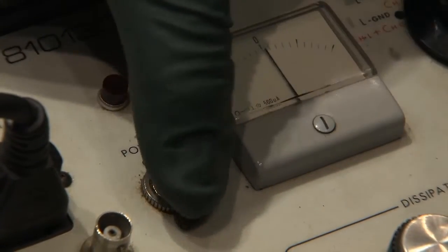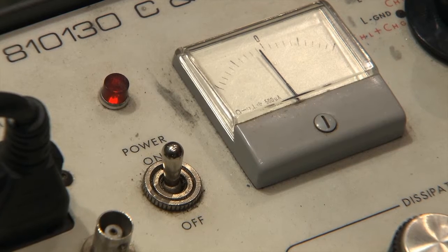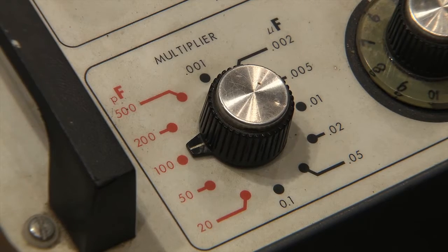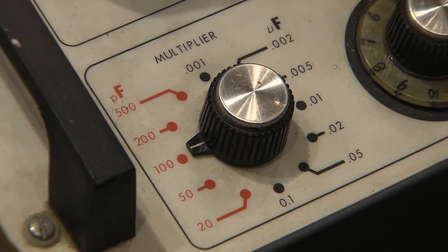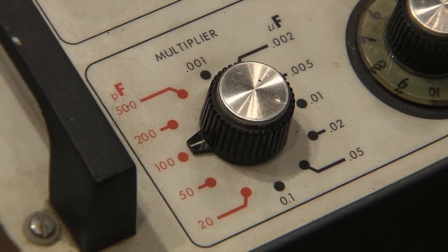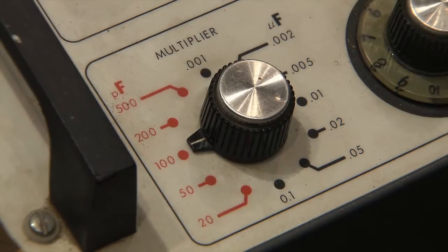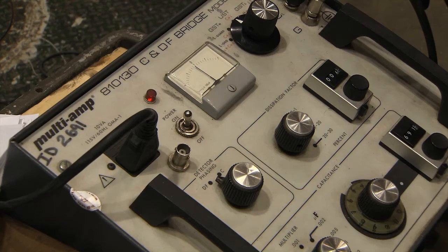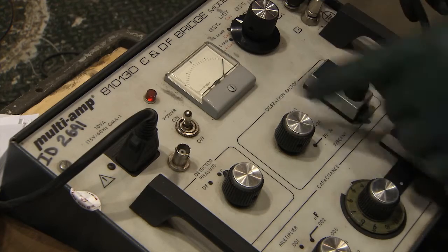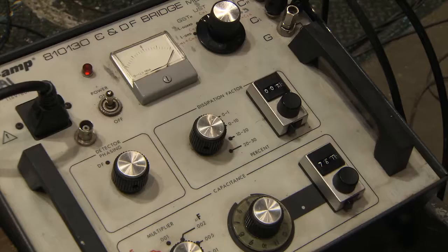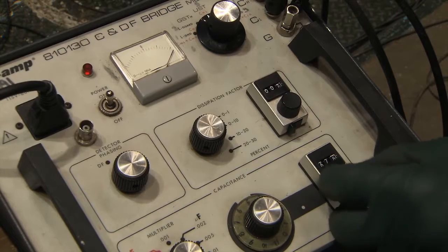Begin by turning the power switch to on. Okay, it's on capacitance right now. Dial the multiplier switch to select 100 on the picofarad scale on the left side. Dial the detector phasing switch to select C for capacitance. Now I'm going to be adjusting this, trying to zero it out. Yeah, I think that works better.